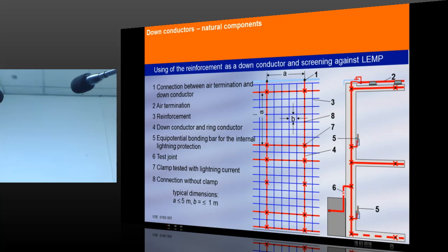See in this particular case, this red line from top to bottom is maybe a column, or the steel inside a pillar, steel inside the top slab. And you see this particular place where the reinforcement is taken out of the building and then connected to number 2. Number 2 is nothing but air termination. It is connected to a mesh, and then a small portion is connected to protect the parapet.